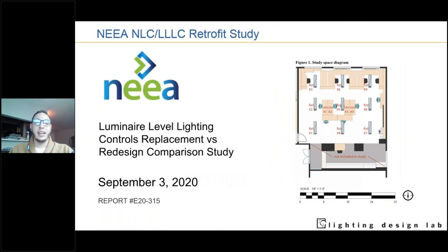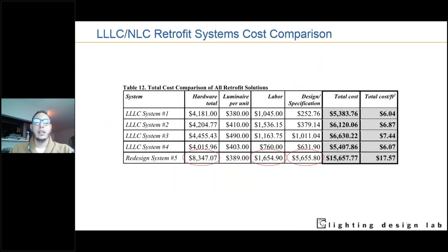The Northwest Energy Efficiency Alliance recently released a comparison study where they had a 1,000-square-foot room with 9 fixtures that were 2-lamp, 32-watt fluorescent 1x4 fixtures. They replaced these 9 fixtures with 4 luminaire level lighting control systems and 1 redesigned network lighting control system, and wanted to compare cost and savings. Looking at installation cost, on the right-hand column, the 4 luminaire level lighting control systems all had rather low costs, around $6 to $7 a square foot, while the NLC system added a good amount of cost even ahead of time.